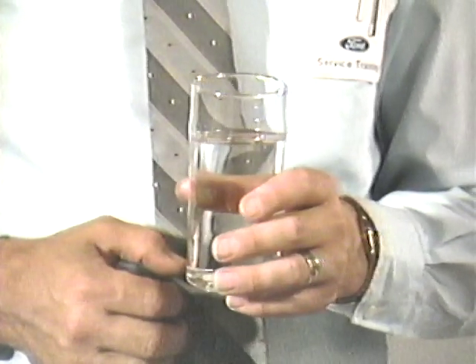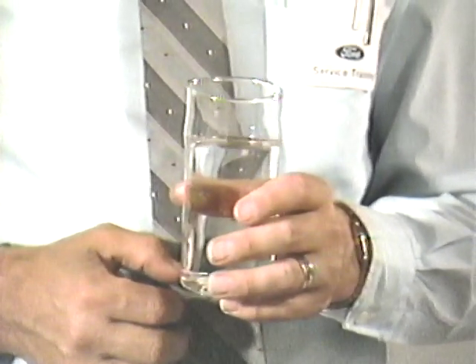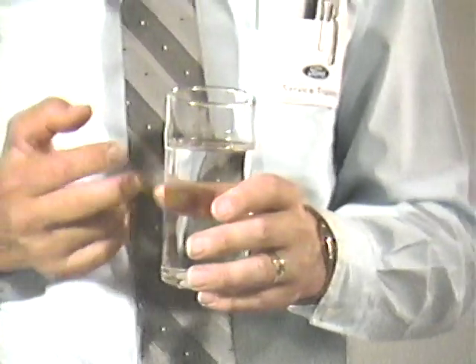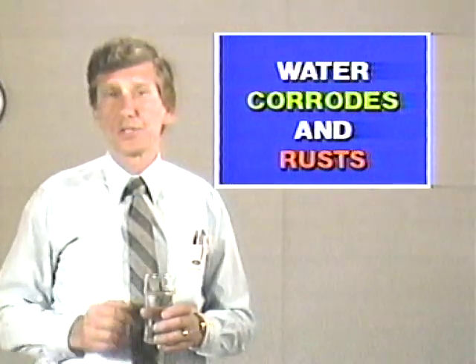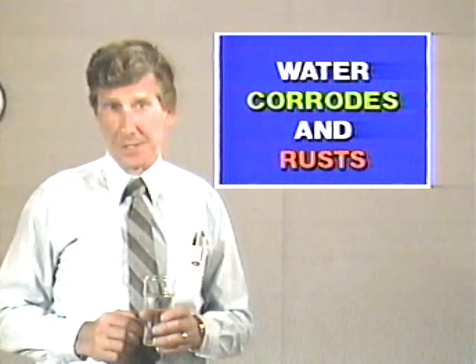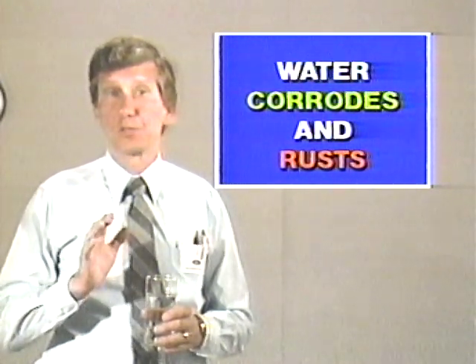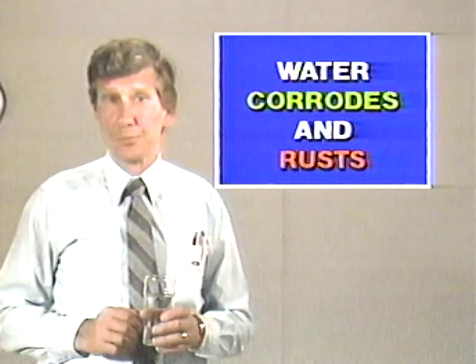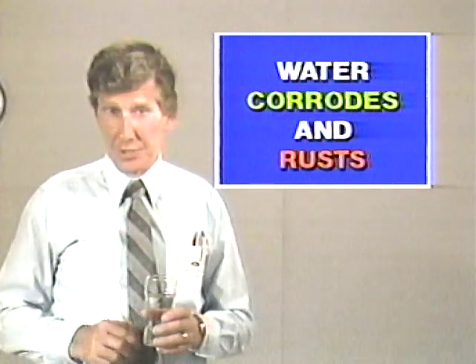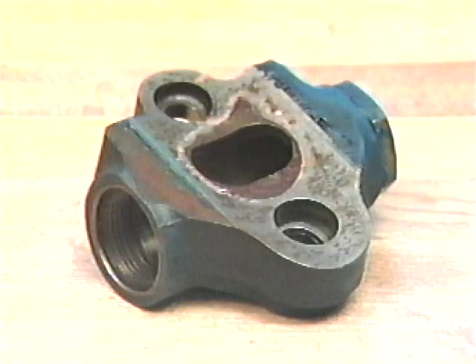Another threat to the fuel system's precision parts, besides dirt, is water in the fuel. Now, this water may be good for you and me, but it's murder on the fuel injection pump. Water corrodes and rusts finely engineered working surfaces. The effects of even the smallest amount of water in the fuel injection pump can be just as disastrous as those of dirt. Water causes corrosion, which can result in rapid wear and even pump seizure.